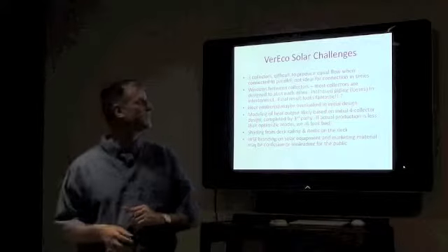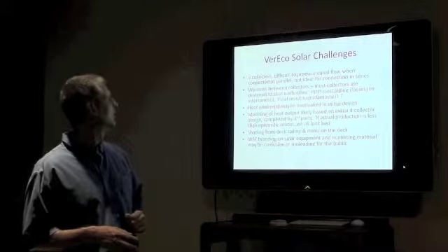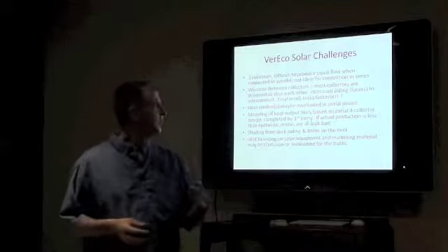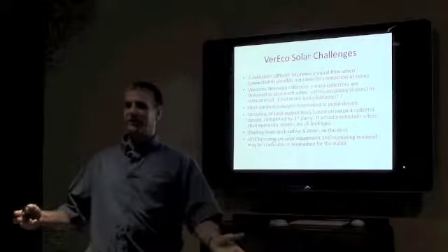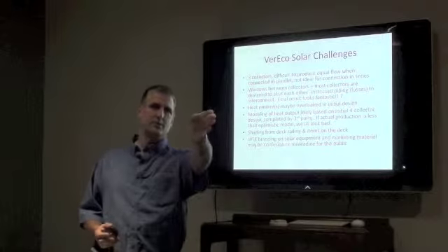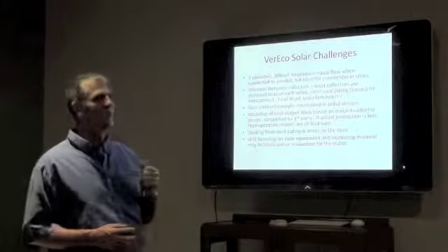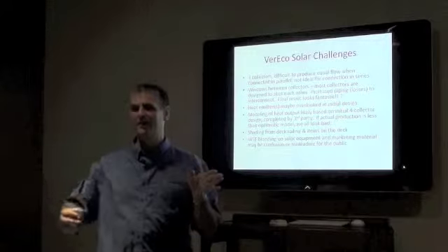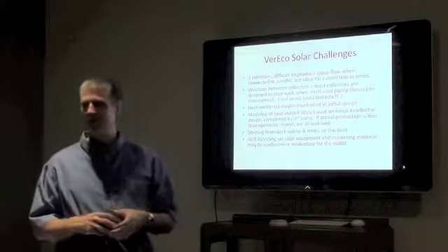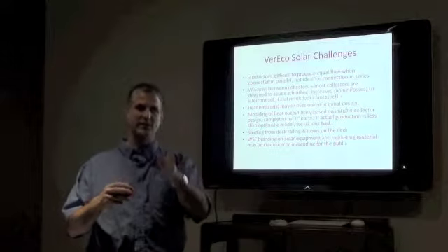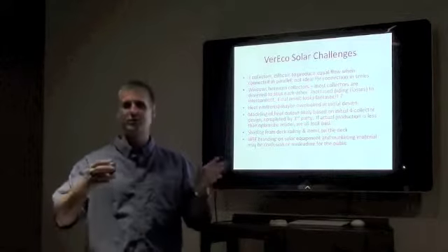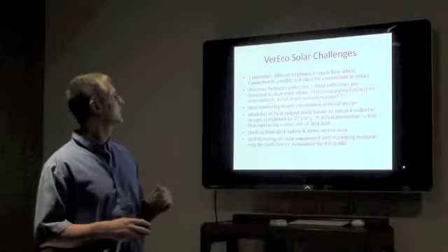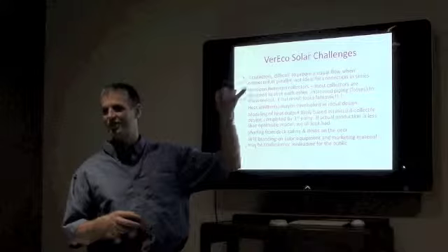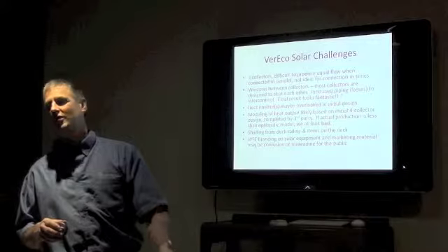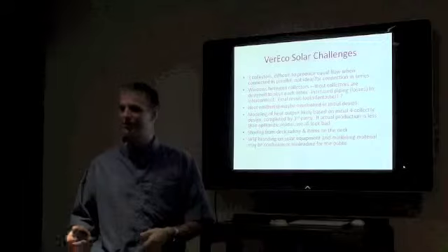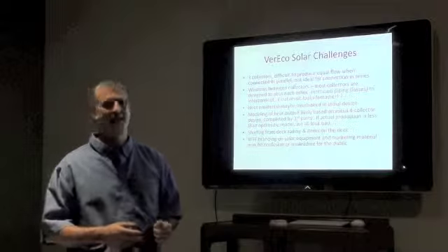So, some of the challenges on the VerEco home. The first one was, originally we talked about putting 4 collectors on this home, and there weren't going to be any windows over here. So we were just going to put 4 collectors side by side, which is the way the manufacturer intends them to be mounted. But then Ron wanted to put windows in, so we didn't have room for 4 collectors. We used 3, and we put spacing between them. One problem is 3 collectors are difficult to mount so that you get equal flow to all collectors. Same as if you have 3 storage tanks, it's difficult to plumb to get the exact same flow through them.